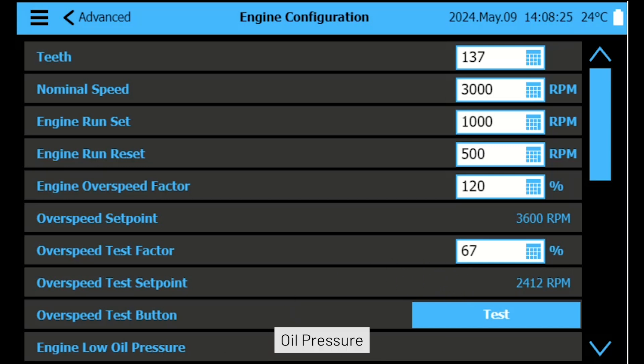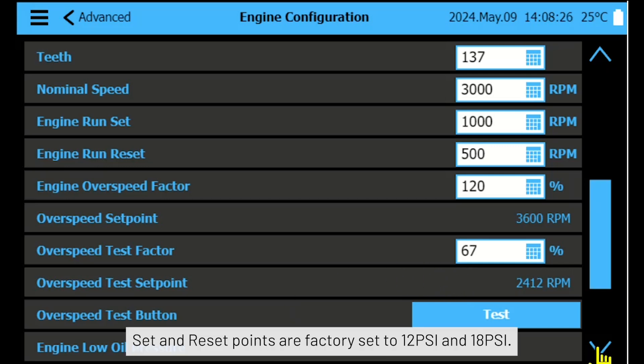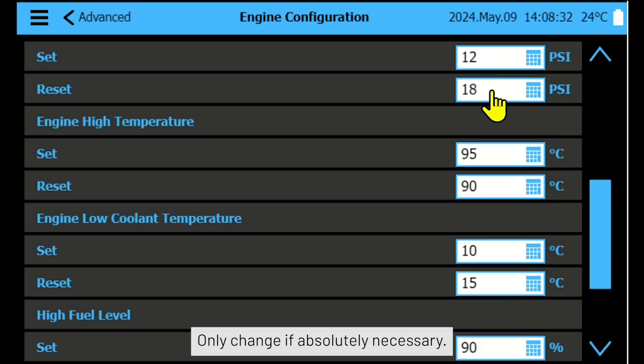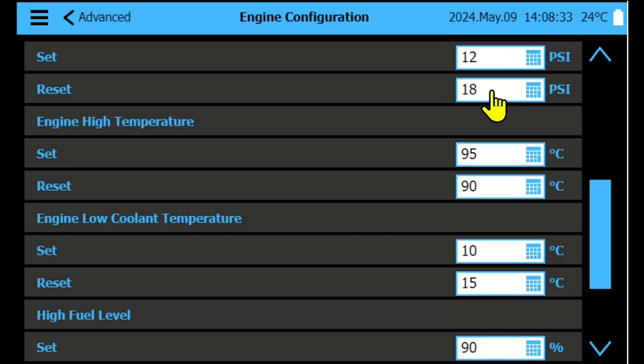Oil pressure: set and reset points are factory set to 12 PSI and 18 PSI. Only change if absolutely necessary.